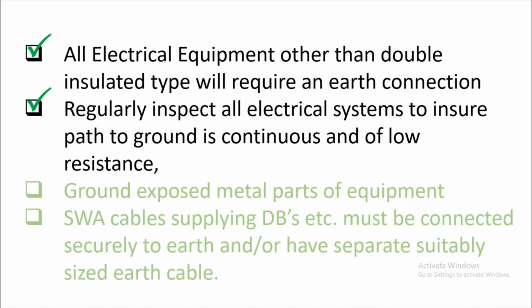So make sure that all earthing connections are continuous on electrical equipment, electrical appliances, and even in the building. Why do we need it in the building? Because, for example, when lightning strikes the building, it will not go directly into the building. It will go to the lightning rod, and the earthing will transfer all the stored energy to the ground, not in the building. Ground exposed metal parts of the equipment.